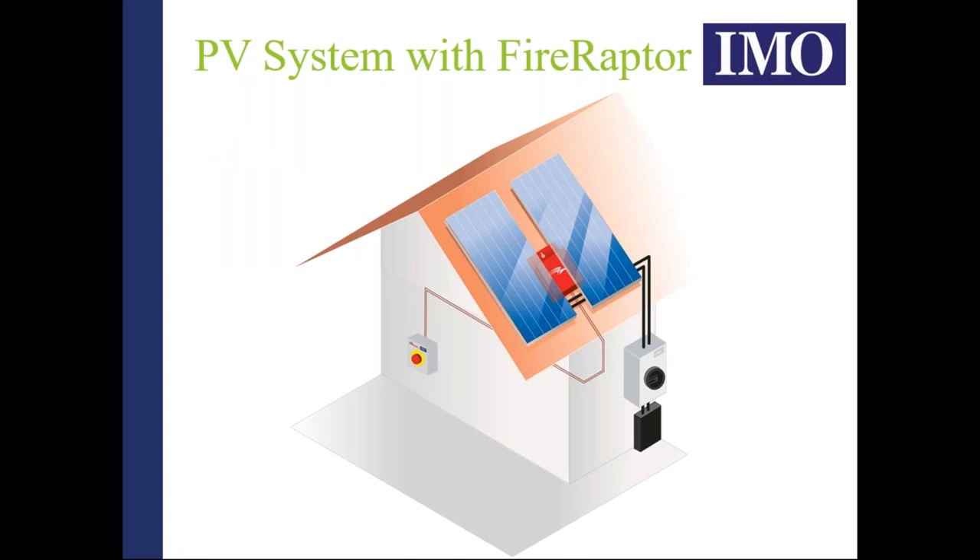This enabled us to consider further what our IMO Fire Raptor rapid shutdown system does, and meant that constraints previously in the 10-foot boundary become much narrower within the one-foot boundary. As you'll see in the next graphic, the IMO Fire Raptor is actually installed to fulfill the requirements of this very small array boundary — the Fire Raptor is actually mounted behind the panels.